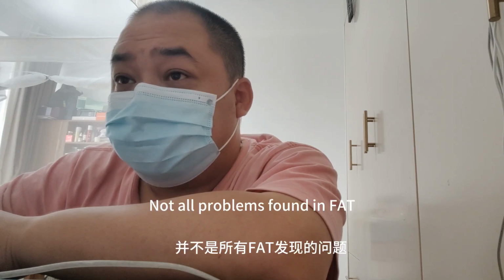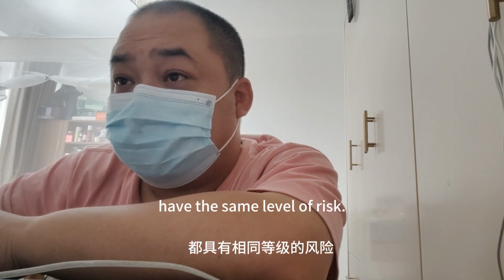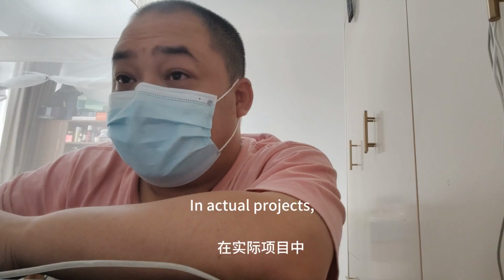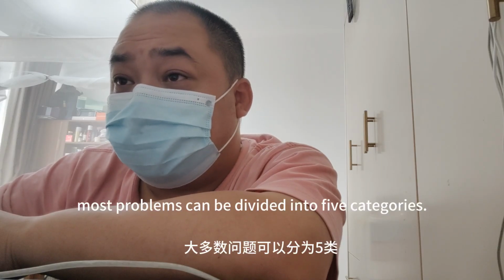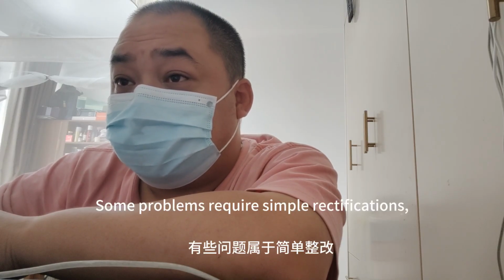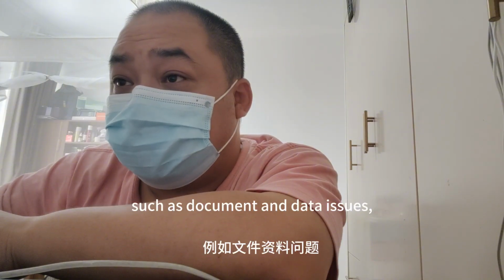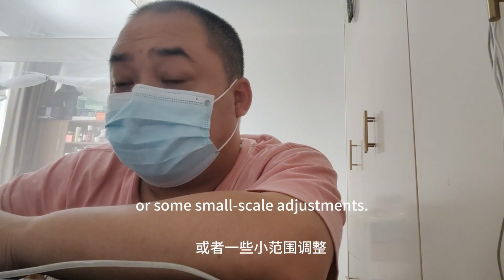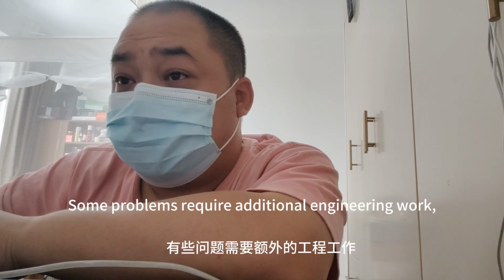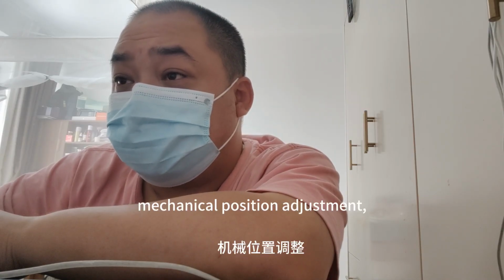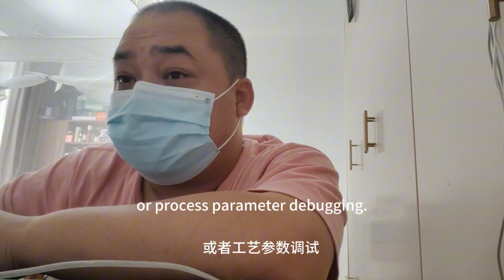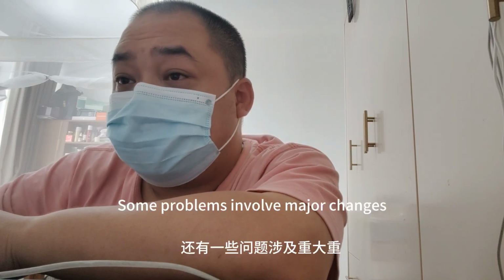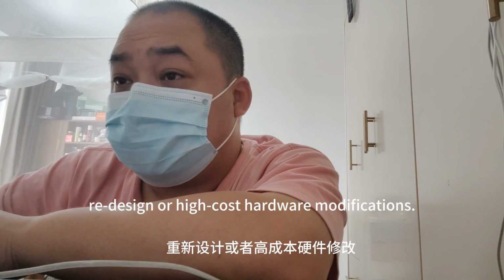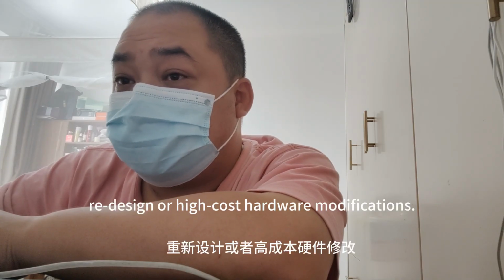Technical analysis: not all problems found in FAT have the same level of risk. In actual projects, most problems can be divided into 5 categories. Some require simple rectifications, such as document and data issues, or some small-scale adjustments. Some problems require additional engineering work, such as PLC program and mechanical optimization, position adjustment, or process parameter debugging. Some problems involve major changes, redesign, or high-cost hardware modifications.